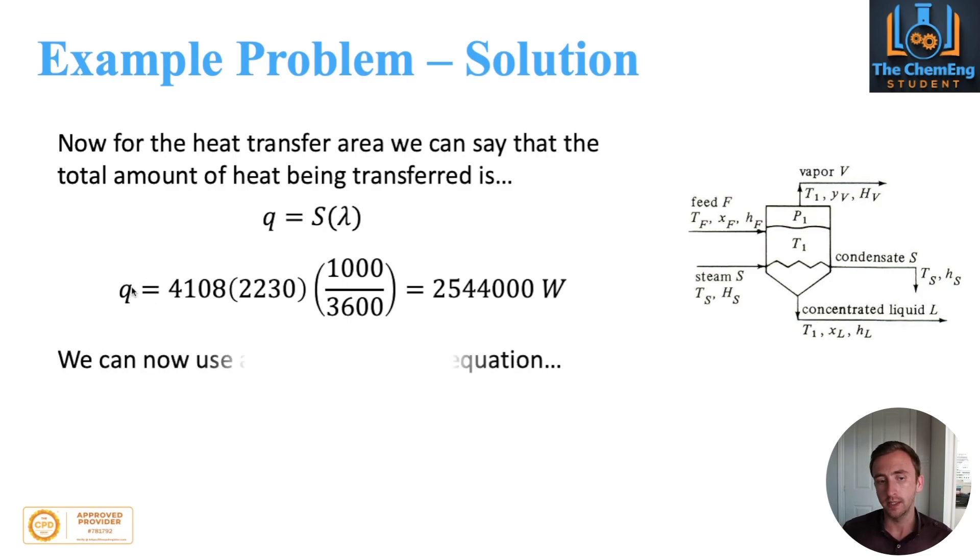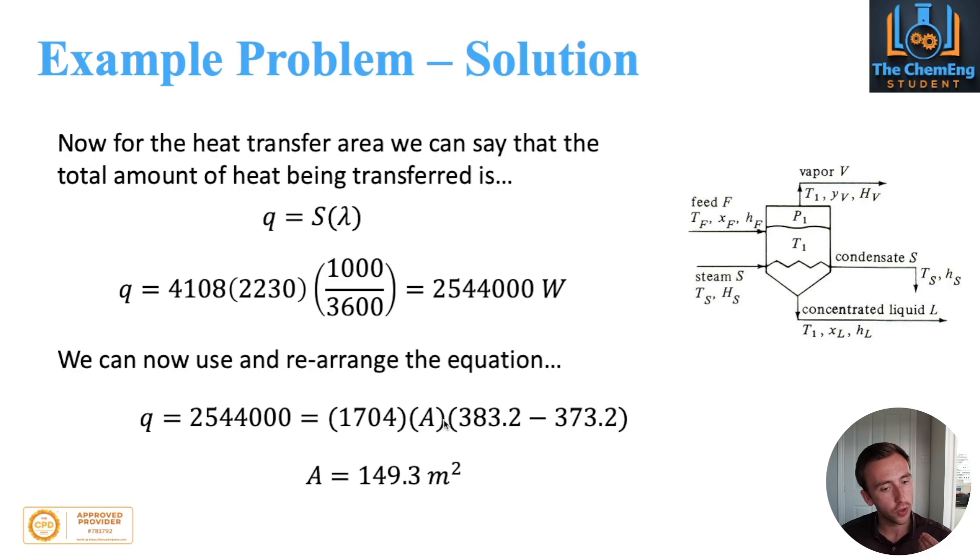Now we know what Q is, we can then rearrange Q equals U A delta T, because the only unknown here is A. We now know what Q is, that's the amount of heat or the power. We know the overall heat transfer coefficient. We know our temperature difference. The only thing we don't have is A. When you solve the numbers, you take these away from each other, multiply it by that, divide it by 2.544 million. We work out that in order for this evaporator to meet the criteria, we need a heat transfer area of 149.3 meters squared. And that's how you would go about solving a single effect evaporator system.